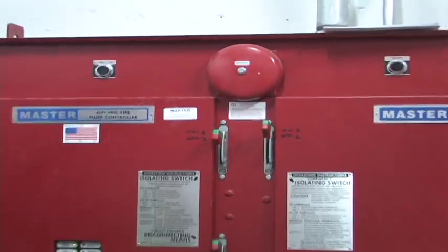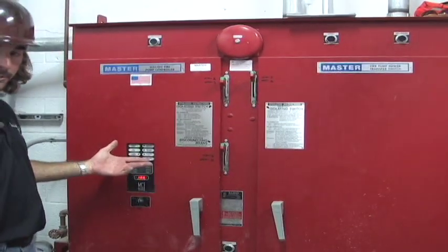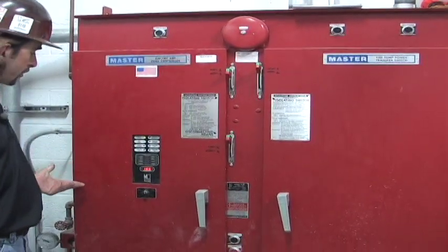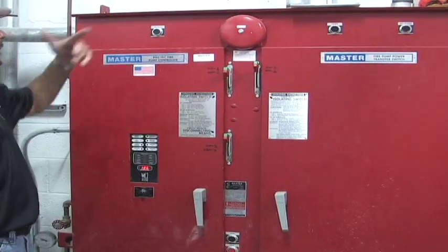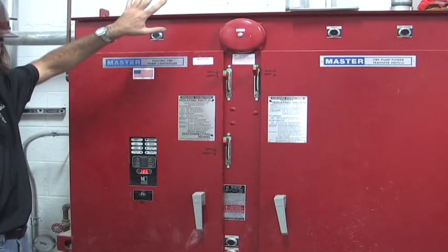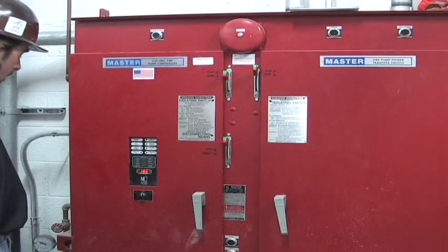We're going to start the pump with the loss of pressure. We won't let it run to 10 minutes right now. Just show how it starts up, and show that the pump running does come back to the fire alarm panel. All right.